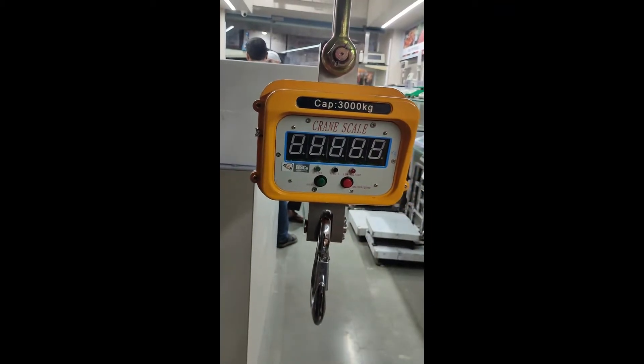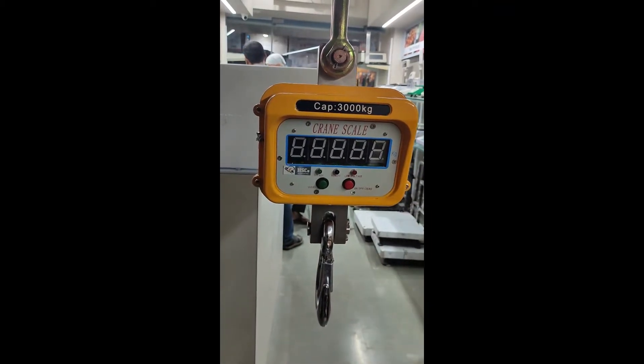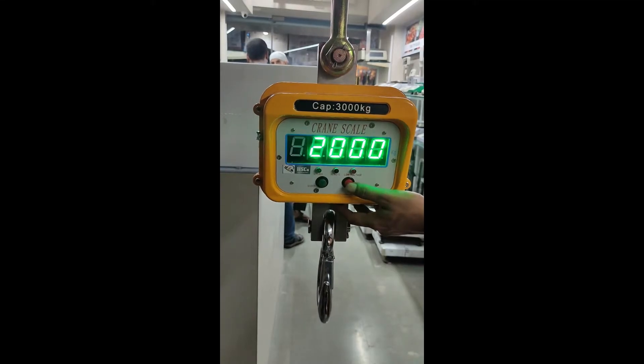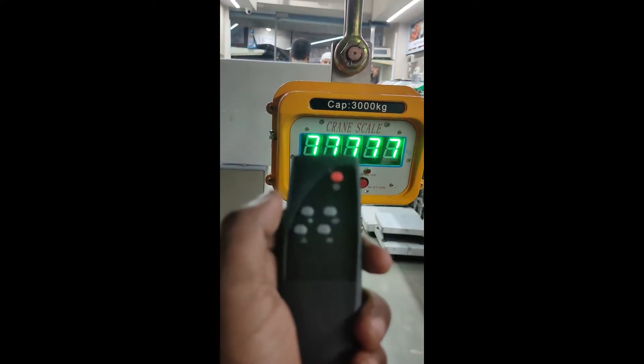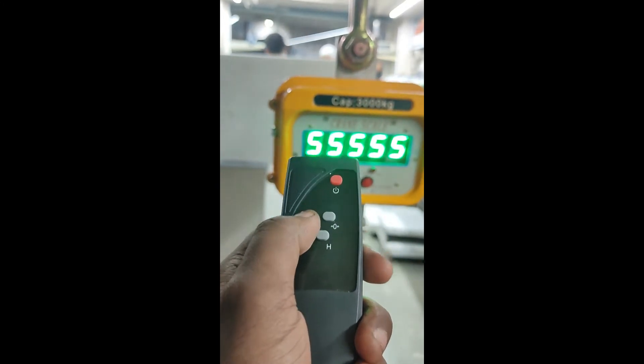Now we are going to see how to do calibration of this crane scale. For that, first switch on the scale. Before the scale shows zero, we have to press this button. Before it is showing zero, now it will show P0.00.